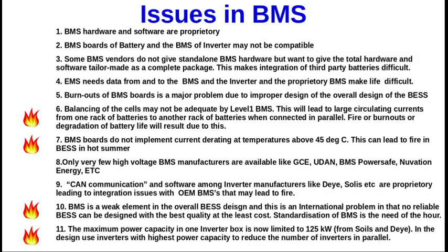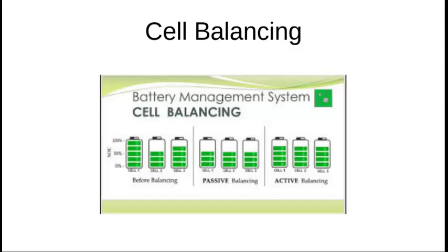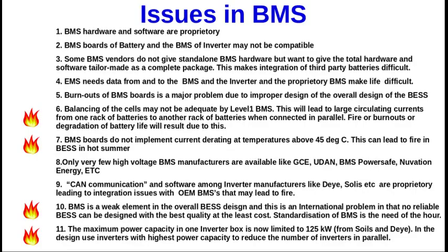Point number 4. The energy management system, EMS, needs data from and to the BMS as well as the inverter, and the proprietary nature of the inverter and BMS makes life difficult. Point number 5. Burnouts of BMS boards is a major problem due to improper overall design of the BESS. Point number 6. Balancing of the cells may not be adequate by the level 1 BMS. This will lead to large circulating currents from one rack of batteries to another rack of batteries when connected in parallel. Fire or burnouts or degradation of battery life will result from this.